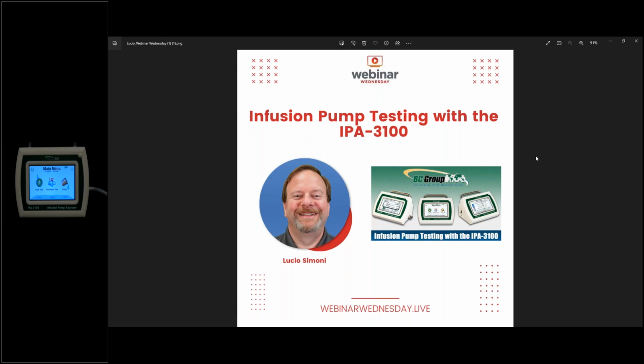Okay, and can I test a syringe pump with this unit? Absolutely. So the 3100, you can pretty much use any pump that you have, with the exception of PCA pumps. So anything with a bolus delivery, if you're looking to measure the time in between boluses or the bolus volume, that sort of thing for a PCA pump, you would need the IPA 3400, which has that additional measurement mode. So the 3100 here, this can measure all the pumps except for PCA.